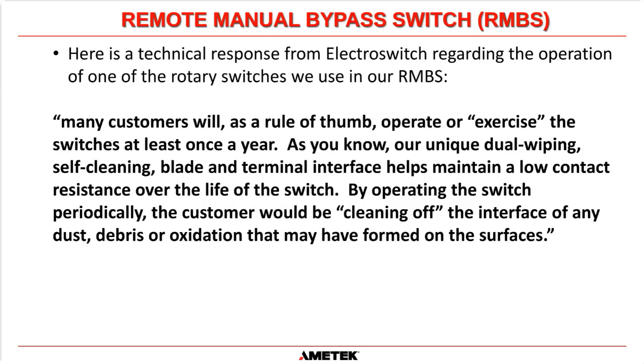So if you leave it in the normal position for, say, 5 years, that means the bypass contacts are open. And when they are open, they are susceptible to things in the environment, especially corrosive things in the air. Sorry for the poor description there, but if you have maybe a little bit of H2S in the air or something like that that can attack the contacts, then that will cause them to have a high resistance. And then when one day after 5 years you move it to the bypass position, you may not make a good contact and you could in theory drop the load.